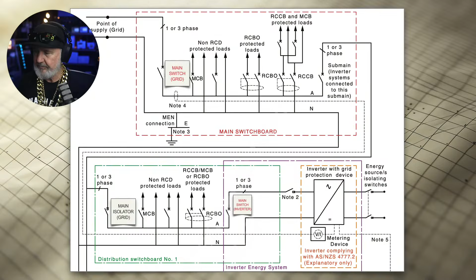Okay, so single phase point of supply - we've now allowed much bigger single phase connections. An aggregate of single phase inverters shall not exceed 30 kVA or 130 amps. Wow, there's not many single phase inverters that big, but you could aggregate them. So Jeff might have put in 3 10 kilowatt SIGs, single phase, and paralleled them all together for an awesome single phase system - up to 30 kVA.